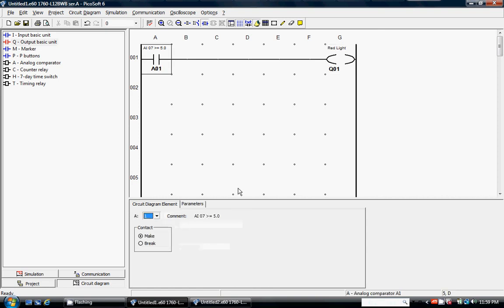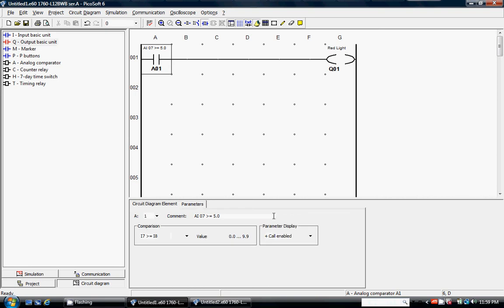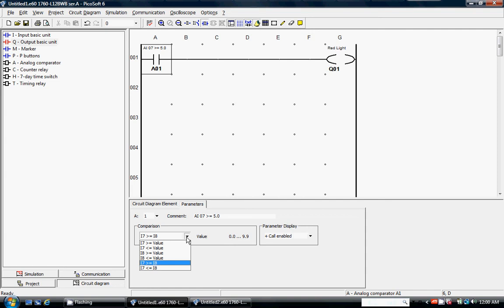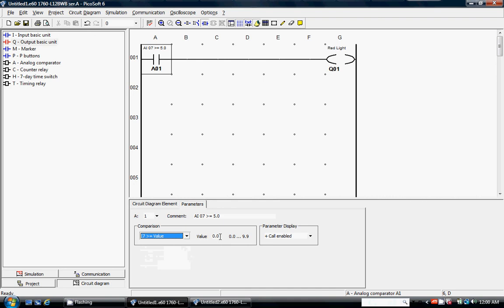I need to do more with the analog input by selecting the parameters tab, and here's where we have our selection of six different types of comparisons. By default, input 7 is compared to input 8, so if you do nothing you're going to compare two values on the inputs rather than an input to a value, and that's what I want to select. So I'm going to say input 7 is going to be greater than or equal to a value, and I've decided I want it to be 5.0, so I'm going to leave it at 5.0.